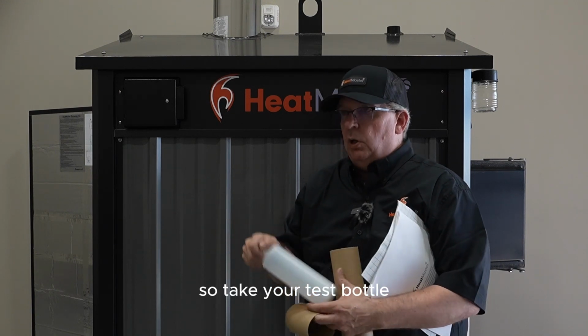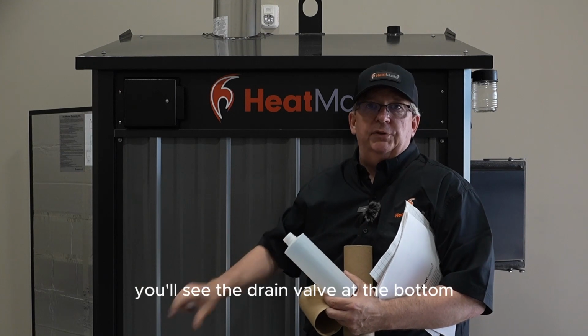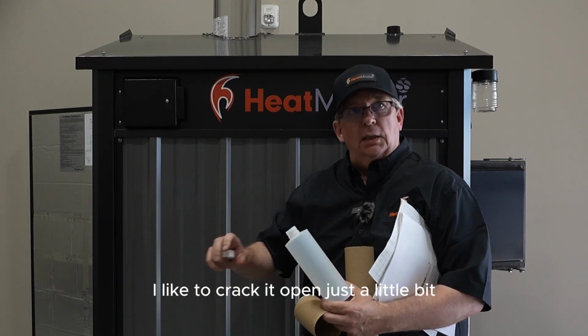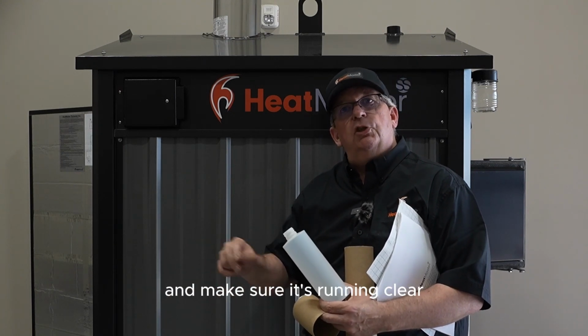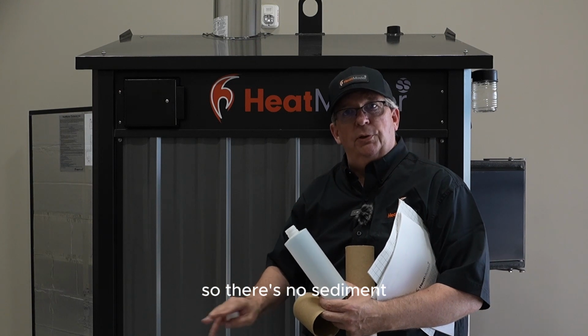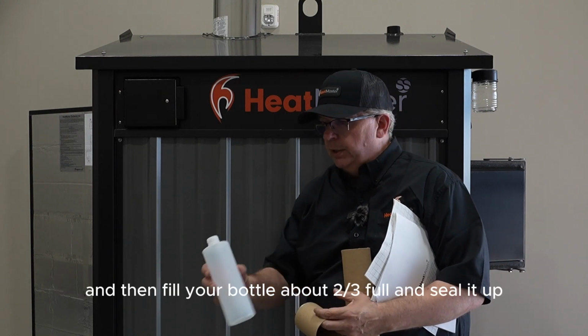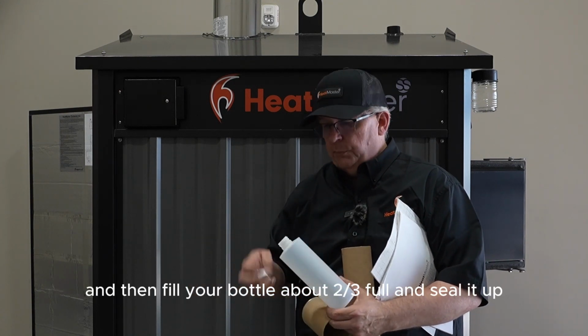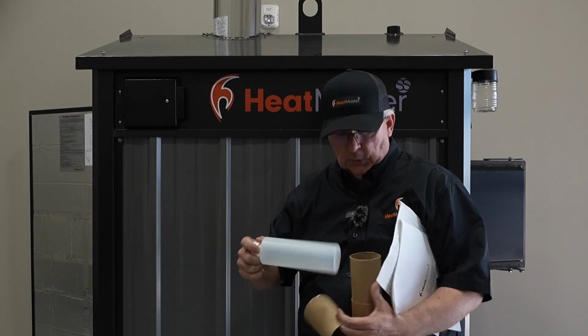So take your test bottle, and on the back of the furnace, you'll see the drain valve at the bottom. I like to crack it open just a little bit and make sure it's running clear so there's no sediment or anything on the bottom of the furnace. And then fill your bottle about 2/3 full and seal it up.